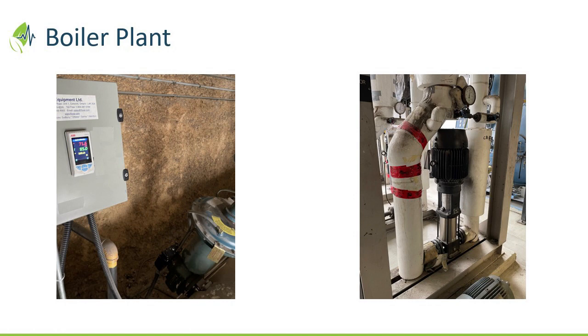So if these aren't working properly, what happens to the efficiency of the boiler? How does that affect the boiler? It declines because you're pulling the heat energy through the boiler at a rate that it's not supposed to be, and you just cannot absorb the heat energy. So it's just bypassing the boiler and going right up the stack. It also can cause problems. You can have nuisance trips, you can have fluttering, you can have combustion events if you're not careful. So there's a safety piece to that as well. So going back, the work is going to be, let's get the dampers on the economizers working properly so that the flue gases are going through the economizer when we want the heat, and let's get the draft dampers working properly so we don't have too much air rising.